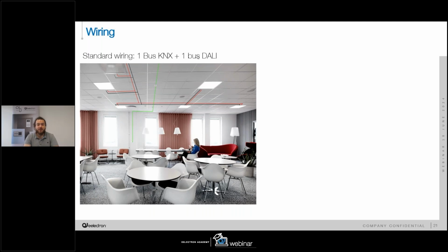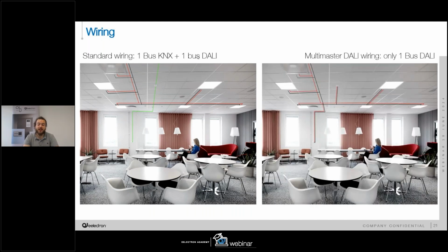Instead, with the new multi-master application gateway, we can wire the push button and the sensor directly inside the gateway. The pro, of course, is that we will have only one bus on the ceiling that arrives also to the push button and the motion sensor, meaning that I don't have to bring the KNX cable to the top of the ceiling anymore. Of course, the HVAC and any other function in the project, like the shading system, weather integration, and so on, can be done very easily in KNX. And thanks to the gateway, we can exchange information between KNX and DALI very easily.